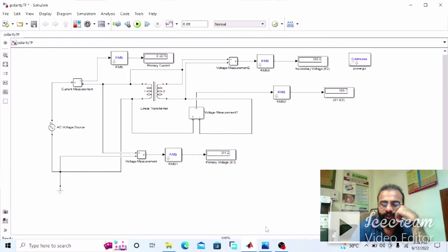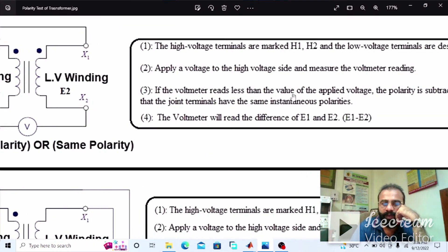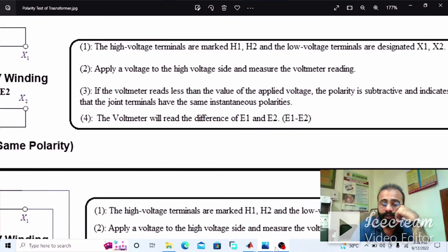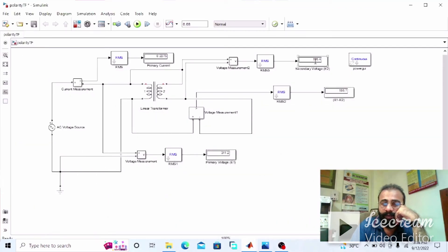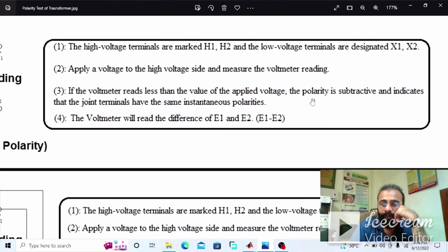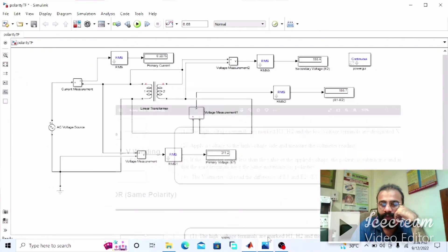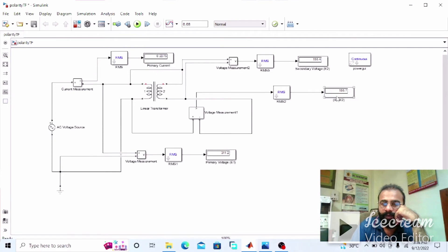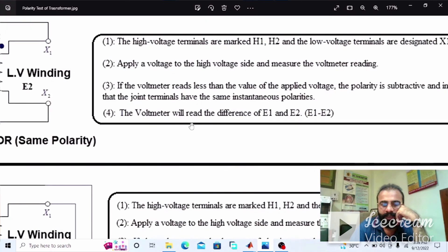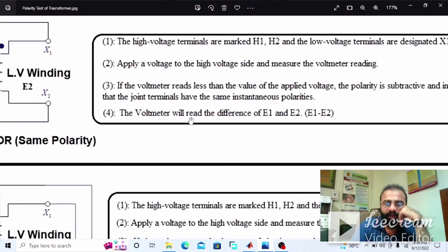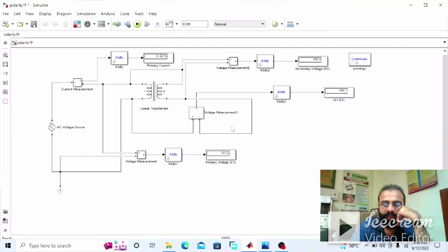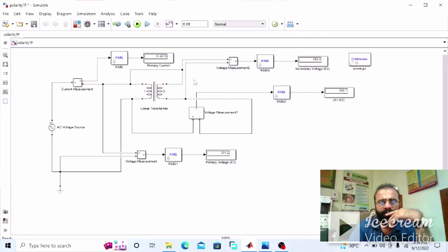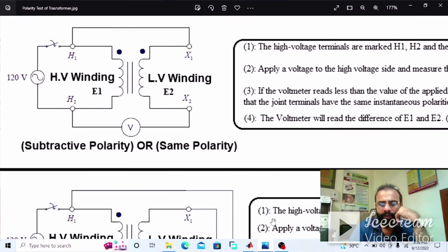This voltmeter value is less than the applied voltage. This is the subtractive polarity of the transformer. If the voltmeter reads a value less than the applied voltage, the polarity is subtractive and indicates the joint terminals have the same polarity. This was the MATLAB simulation of the subtractive polarity or same polarity of the transformer.